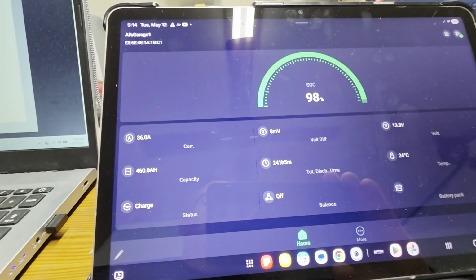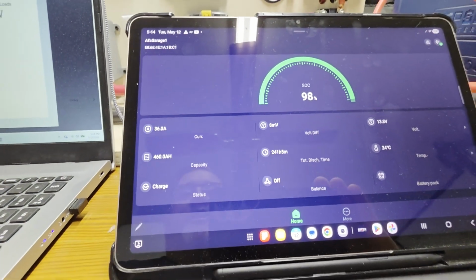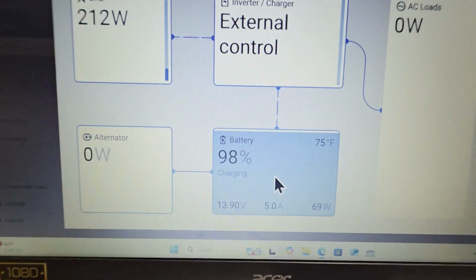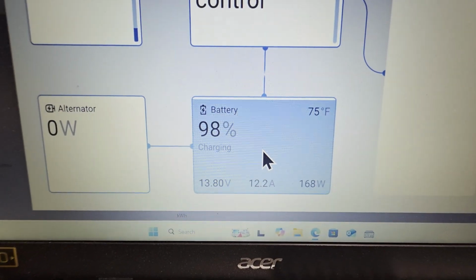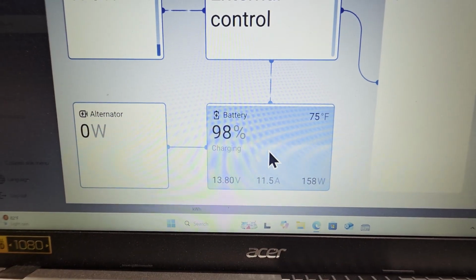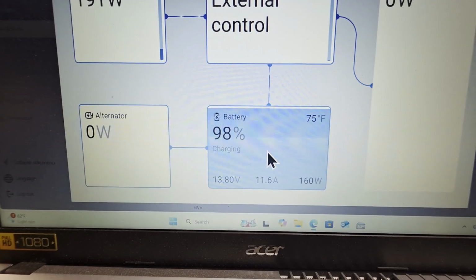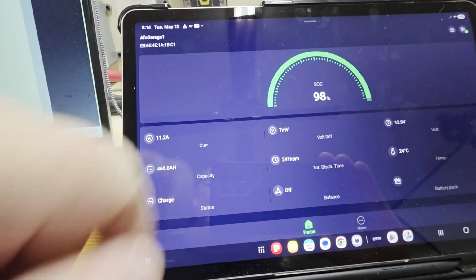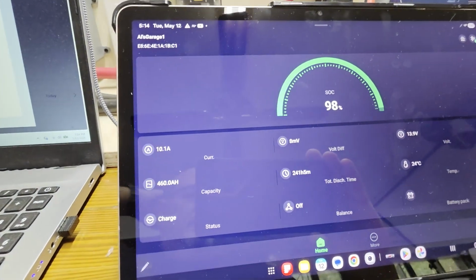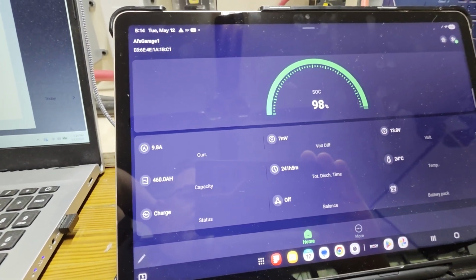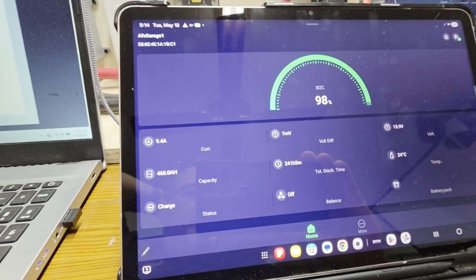We've only reached 8 millivolts because this battery is already balanced. This is essentially the conditions you would need to balance long term. Again, don't touch anything for 12, 24, 48 hours, or however long you need to get that cell delta to 50 millivolts or less, or preferably 20 to 25 millivolts.